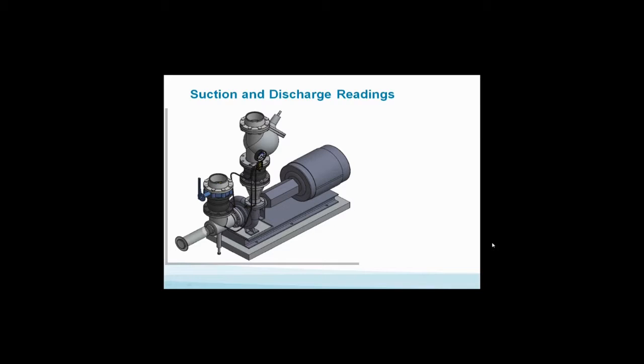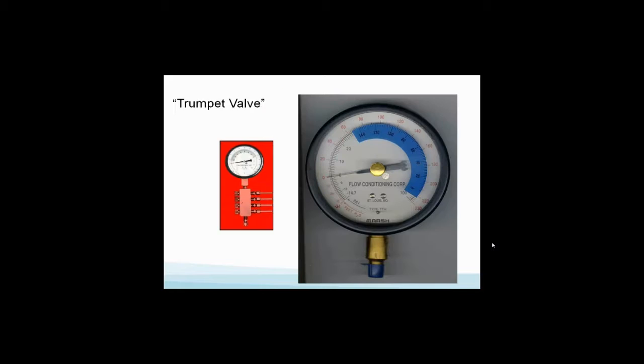So I've got a pump. I want to read the differential pressure across the suction and discharge tappings on that pump to see where it is on that pump curve. So our pump is generating 63 feet of head. The differential pressure across the pump, when I just turned it on in that system, is 63 feet of head.